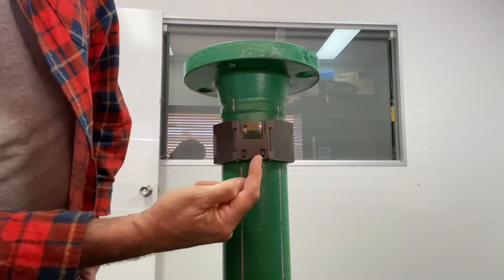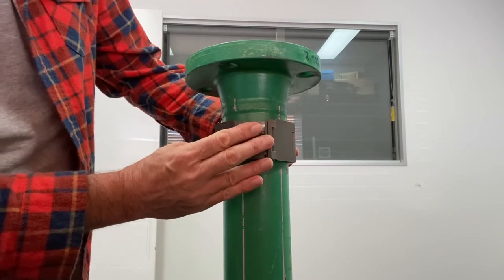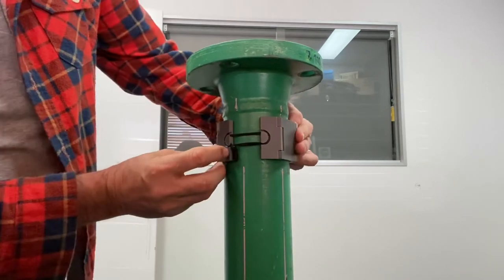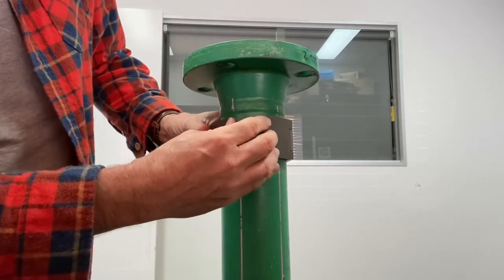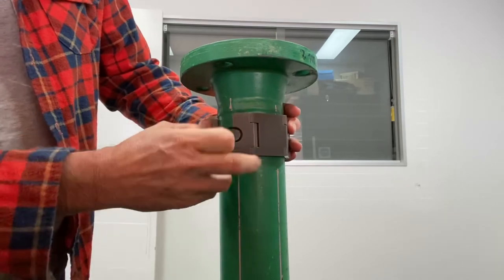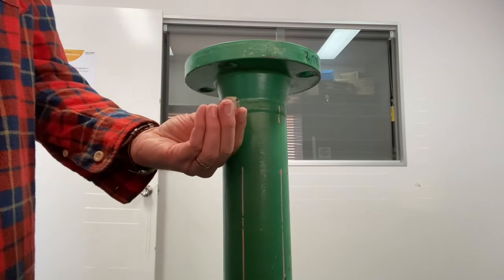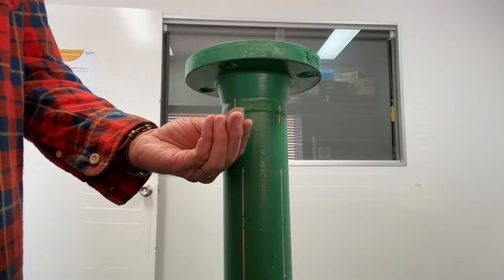An encoder will fit here, so the concept is basically to drive around like this, save the scan, unhook the scanner, and onto the next one. The height limit is basically the height of the probe sitting on top of this wedge.